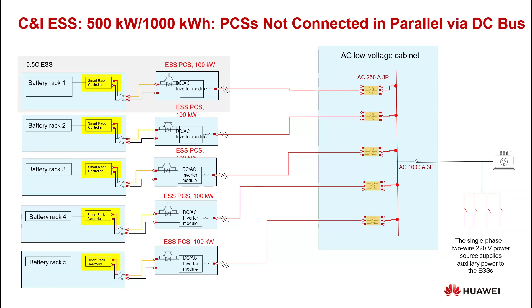Yeah, and of course, one good thing to mention in this case is that when you are putting in a battery, and the same when you put in a PV system, you need to consider the rated current of the electrical cabinets you will be connecting the battery solutions to. If the supply cable uses all the current that is labeled for the cabinet, then you cannot connect batteries there as well. So it's important to notice that also.